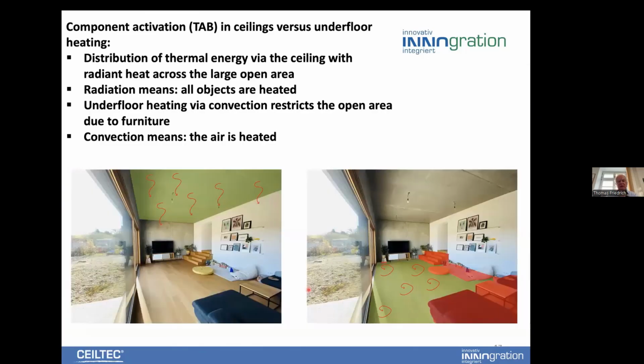I want to mention the difference between bringing energy in through the ceiling versus through the floor. You can see here clearly that the ceiling area is completely free, so you can bring energy into the room through this huge area. Compared to floor heating or floor cooling, it is not possible to use the whole area because you have different elements placed in the room that prevent the energy from coming directly into the room. I think that is one big advantage.